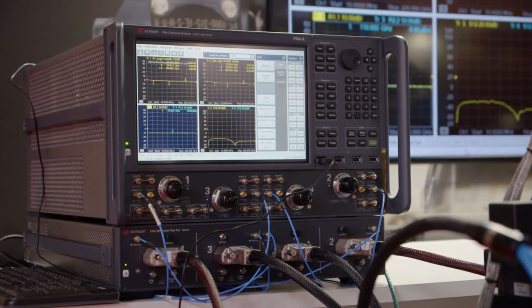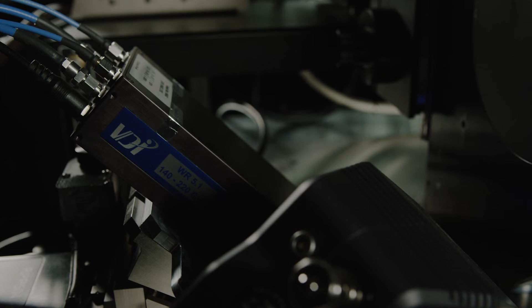So the system, with broadband capabilities up to 170, 220 gigahertz, includes multiple pieces. A single sweep solution based on a Keysight vector network analyzer, the N5291A, which is a millimeter wave system all the way up to 130 gigahertz from very low frequency, 900 hertz. And then the Virginia Diodes sub-terahertz frequency extenders. For this purpose, they have developed extended range WR 5.1 extenders, to cover from 130 all the way to 220 gigahertz.